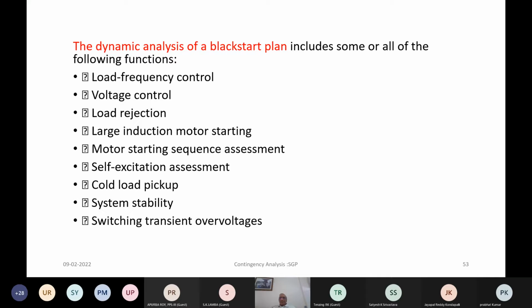can be tried out periodically so that people get used to managing the black start and operating the sub area in an islanded mode with 1 or 2 generators in service. These are the various types of control functions which are necessary during the black start operation: load frequency control, voltage control, load rejection, large motor starting sequence in terms of their capacity, etc.